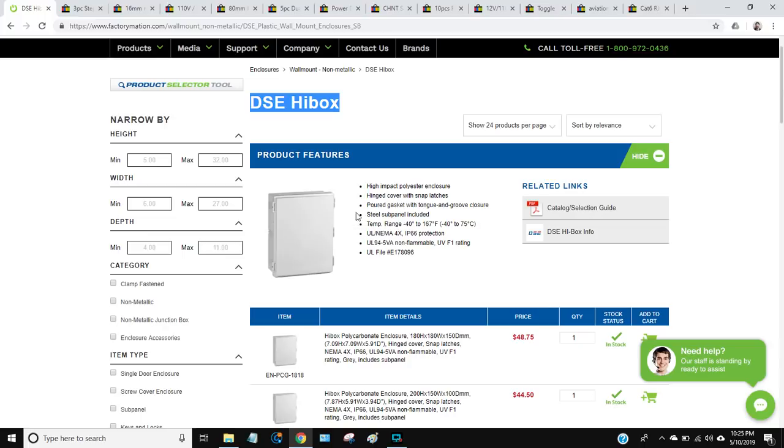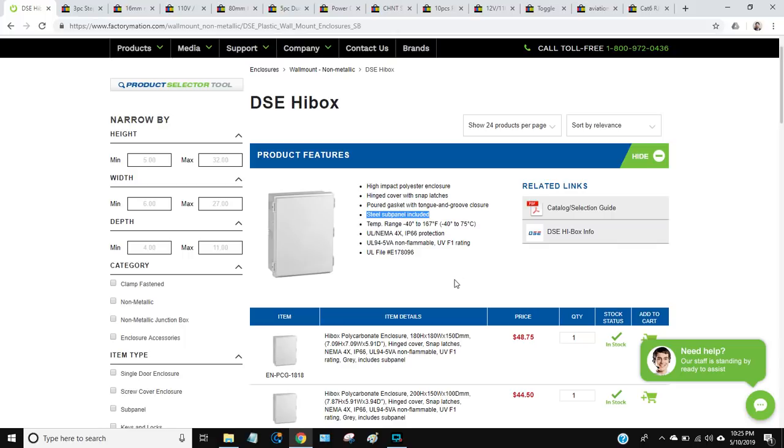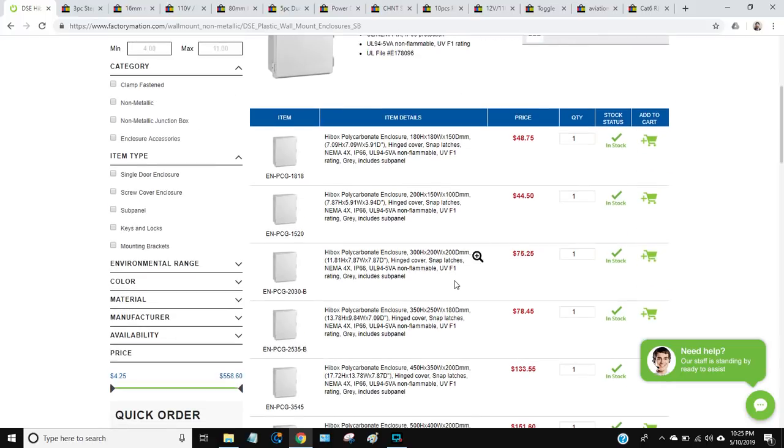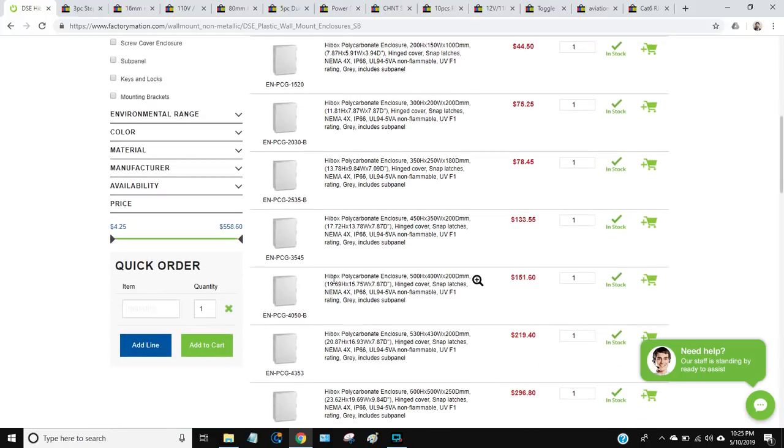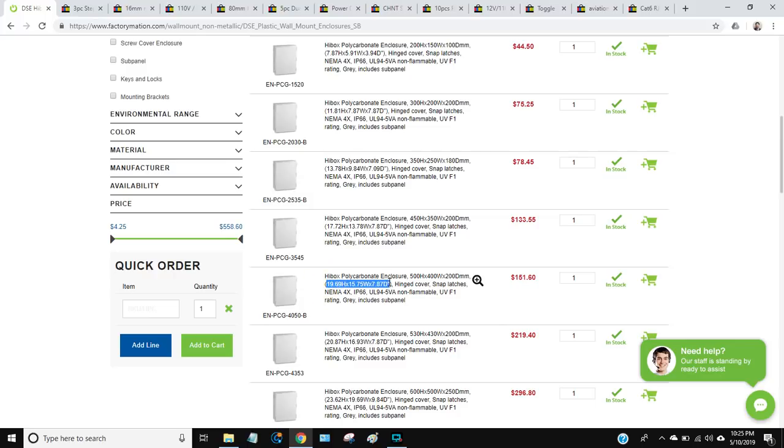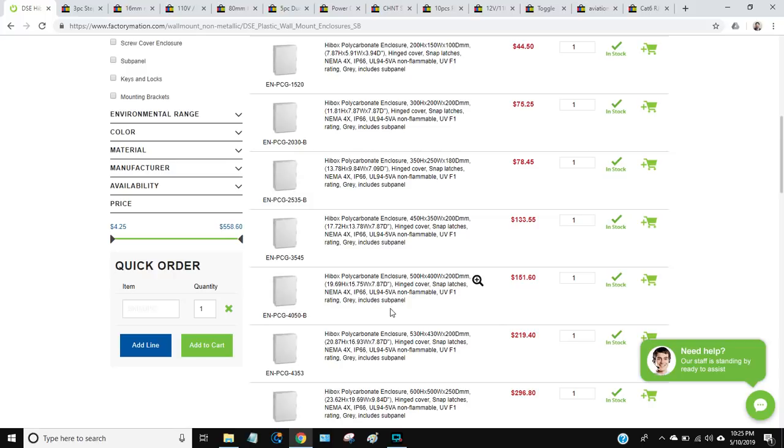These enclosures come with a steel sub panel inside that you can mount everything to, which makes life easier. The size that I usually get is 19.69 by 15.75 by 7.87 with hinged cover and snap latches. At first that might seem maybe a little bit too big, but what I can tell you is when you're working with this stuff you always need more room than you think. It's also nice to have some air space in there so air can move and the electronics can cool off. If you have everything jammed in and consolidated really closely, then it's harder for the electronics to stay cool.